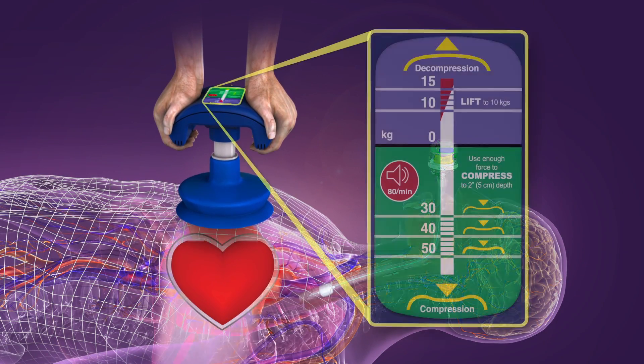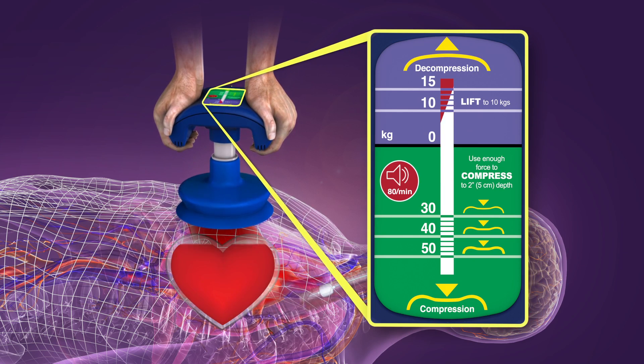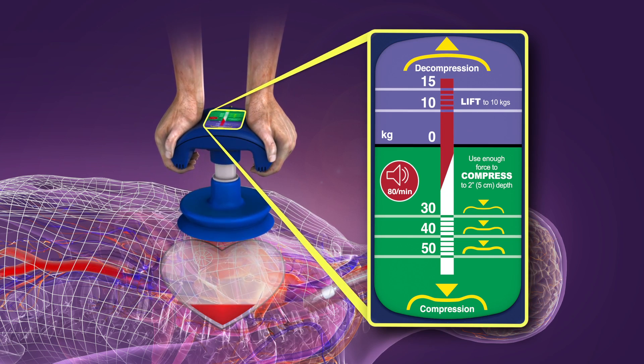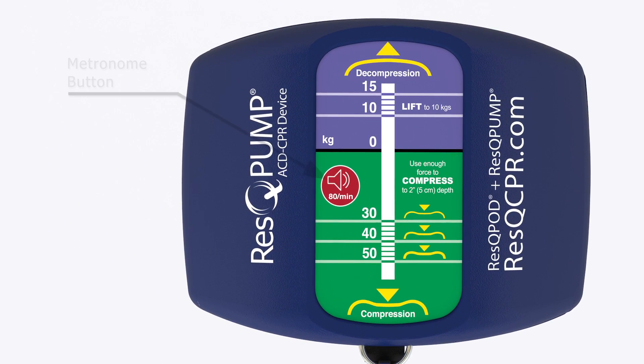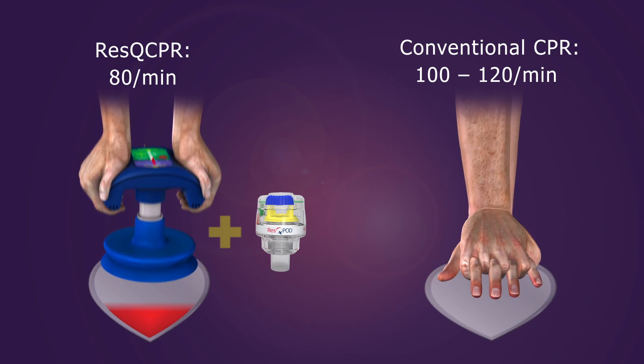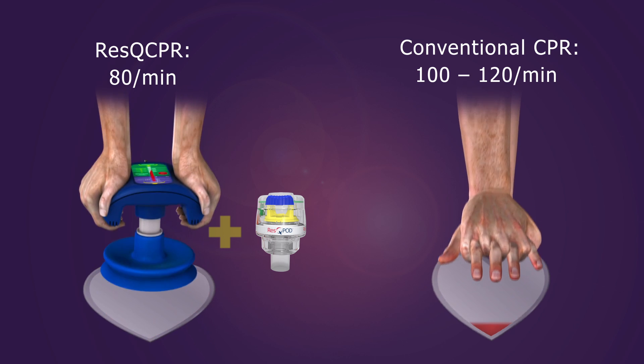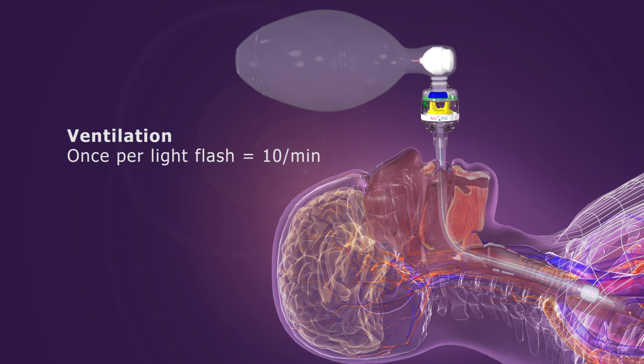A force gauge on the ACD CPR device is designed to guide both compression and lifting forces. A metronome tones at 80 per minute as a guide to the proper compression rate. ResQCPR is performed at a slightly slower rate than conventional CPR to give the heart more time to accommodate the improved preload and cardiac output. Timing lights on the ITD flash 10 times per minute to promote the proper ventilation rate.